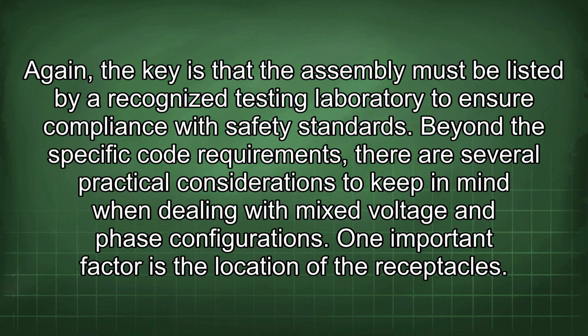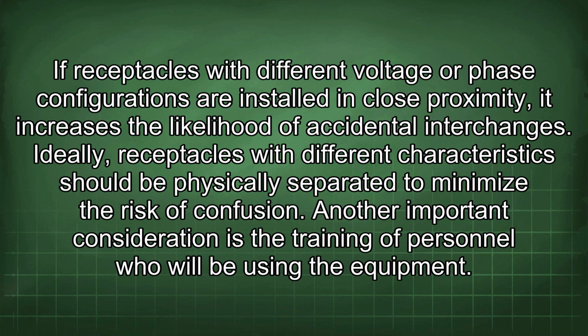Beyond the specific code requirements, there are several practical considerations to keep in mind when dealing with mixed voltage and phase configurations. One important factor is the location of the receptacles. If receptacles with different voltage or phase configurations are installed in close proximity, it increases the likelihood of accidental interchanges. Ideally, receptacles with different characteristics should be physically separated to minimize the risk of confusion.